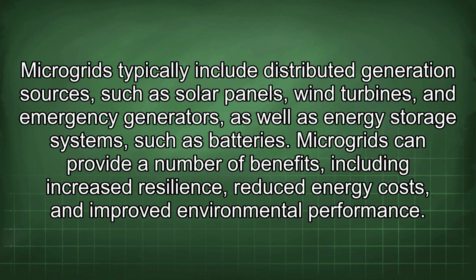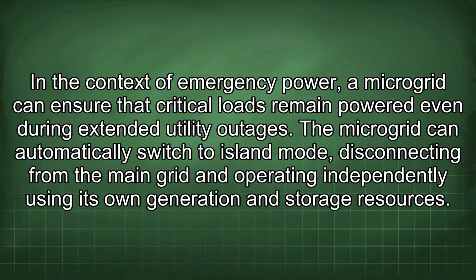Microgrids typically include distributed generation sources, such as solar panels, wind turbines, and emergency generators, as well as energy storage systems, such as batteries. Microgrids can provide a number of benefits, including increased resilience, reduced energy costs, and improved environmental performance. In the context of emergency power, a microgrid can ensure that critical loads remain powered even during extended utility outages. The microgrid can automatically switch to island mode, disconnecting from the main grid and operating independently using its own generation and storage resources.